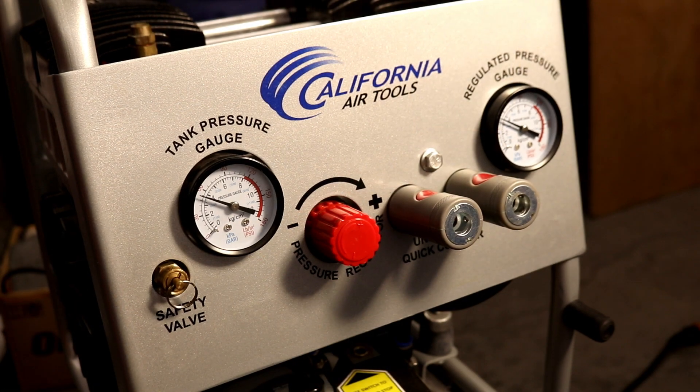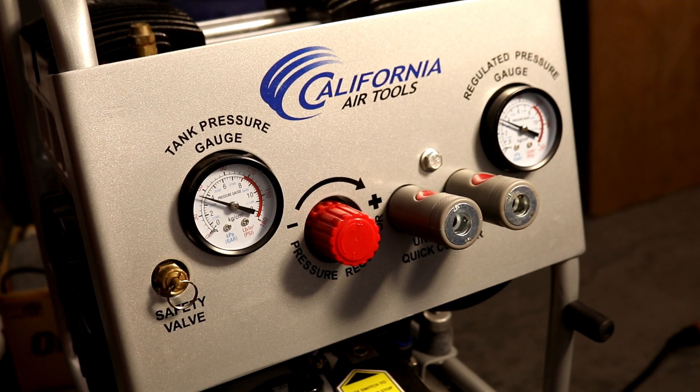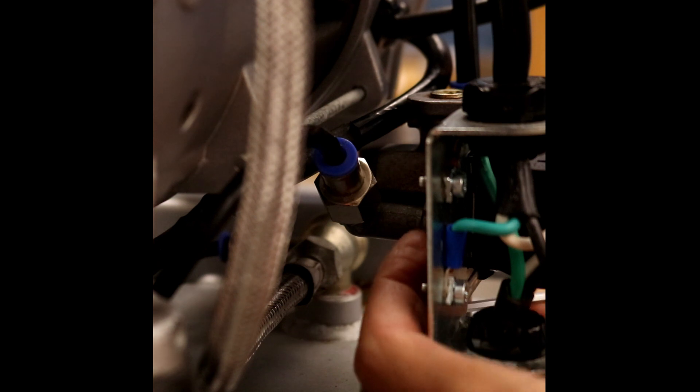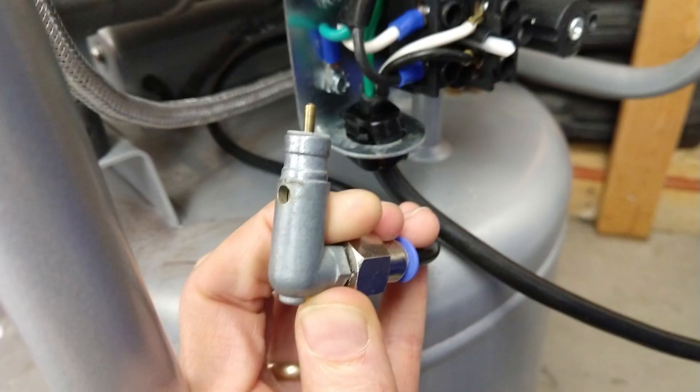The next leak to fix is from the unloader. This leak causes the compressor to run three times longer than needed. The unloader releases cylinder pressure after the compressor stops, and if the unloader does not function, the initial load on the motor will be high, likely stalling and possibly self-destructing the motor.